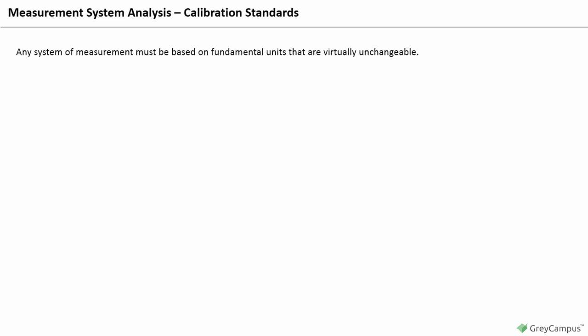to be followed. The various standard bureaus and laboratories then develop primary reference standards which embody the units of measure corresponding to these standard test methods. In practice, it is not feasible for the National Institute of Standards and Technology to calibrate and certify the accuracy of the enormous volume of test equipment in use. Instead, resort is made to a hierarchy of secondary standards and laboratories together with a system of documented certifications of accuracy. When a measurement of characteristics is made, the dimension being measured is compared to a standard.